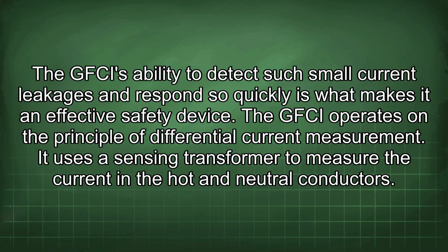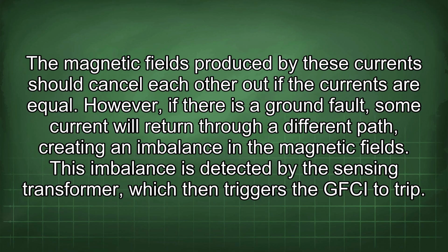It uses a sensing transformer to measure the current in the hot and neutral conductors. The magnetic fields produced by these currents should cancel each other out if the currents are equal. However, if there is a ground fault, some current will return through a different path, creating an imbalance in the magnetic fields. This imbalance is detected by the sensing transformer, which then triggers the GFCI to trip.